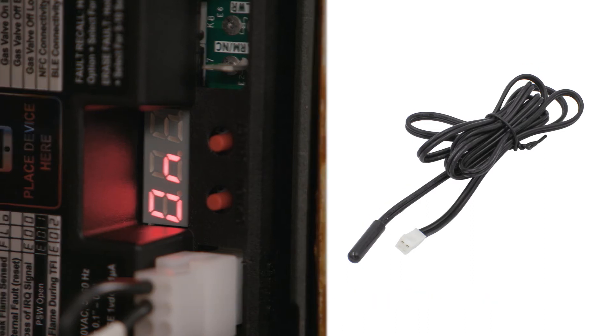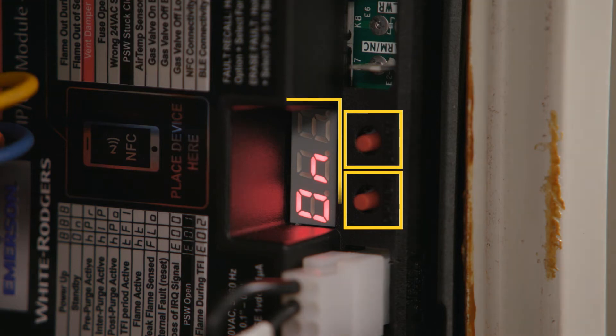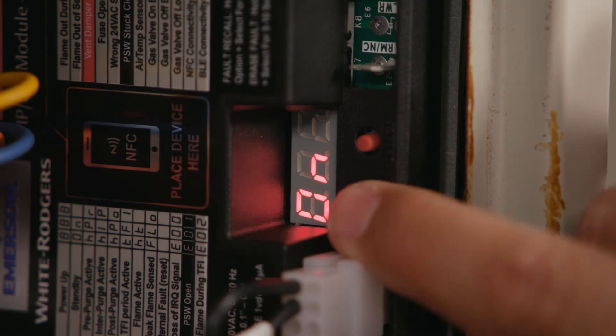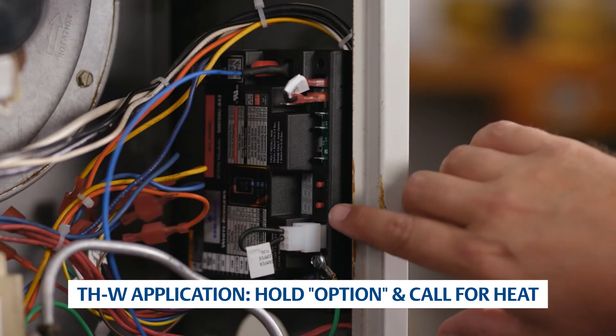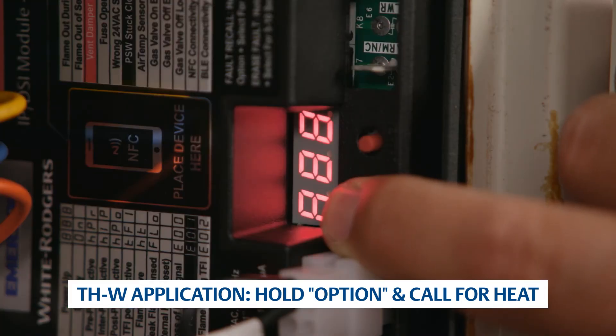If configuration was not completed using the White-Rodgers Connect mobile app, it can now be set up using the Option and Select buttons and the LED display. To enter configuration, press the Option button while the unit is in standby. For applications that have power only to THW, there is no standby mode; to enter configuration mode, hold the Option button for three seconds while simultaneously supplying 24-volt to THW.